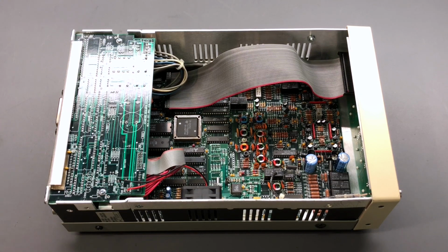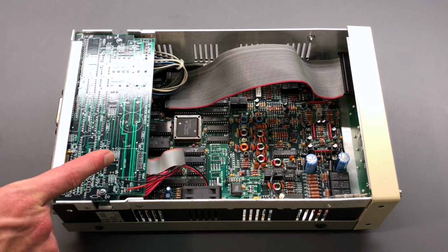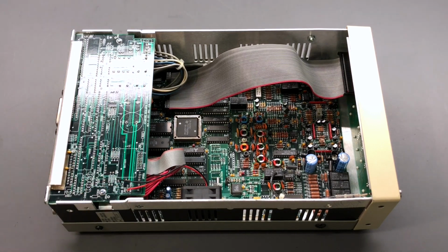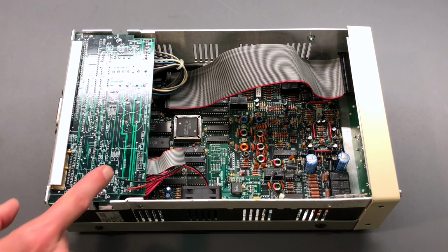That Cal D error that we saw in the front panel is a big clue that this battery may in fact be dead or very, very weak. Now, Stanford Research Systems mentioned that if the Cal D error comes up infrequently, it's really not a cause for concern, and if the instrument is otherwise performing okay, it's really not a problem. But if it's coming up often, which it does on this instrument every time you turn it on, that is a cause for concern, and it often means a problem with the battery. More serious, it may mean that there's a problem with the RAM chip or something like that, but the battery is the most likely thing.